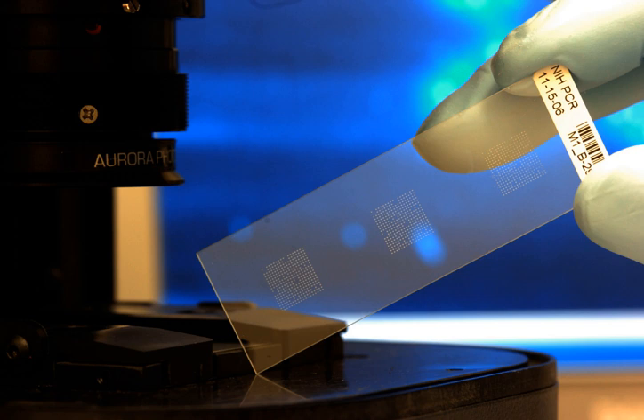Fodor and colleagues developed a unique fabrication process later used by Affymetrix in which a series of microlithography steps is used to combinatorially synthesize hundreds of thousands of unique, single-stranded DNA sensors on a substrate one nucleotide at a time. One lithography step is needed per base type, thus, a total of four steps is required per nucleotide level. Although this technique is very powerful in that many sensors can be created simultaneously, it is currently only feasible for creating short DNA strands. Reliability and cost factors limit the number of photolithography steps that can be done.